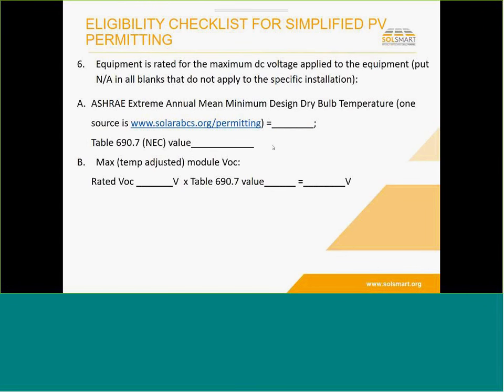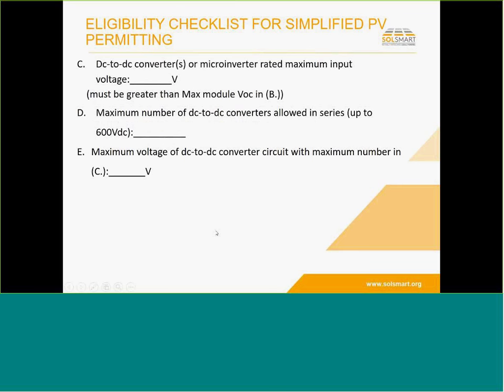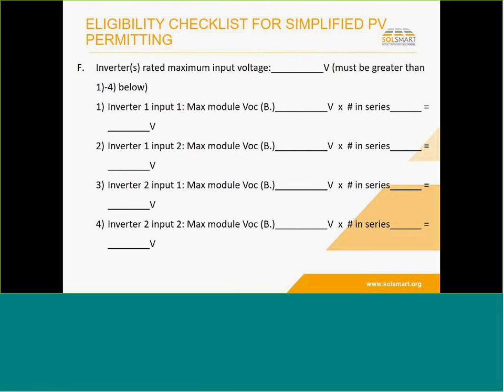And so then we're going to use that data, and we're going to look at the table in the National Electrical Code, and it's going to give us a number like 1.22 or something like that. And we're going to multiply our rated voltage according to that. And then we're going to use that for compliance if we had DC converters, making sure we're not overvoltaging our microinverters or DC converters, and then also use that for any inputs to a string inverter.